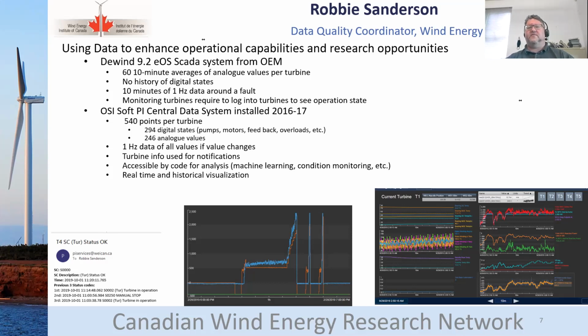Around a fault of the turbine, we would get higher resolution data, 1 hertz and sub-hertz data, for 10 minutes or less around the fault time, but no relevant historical data to go off of. So if you're trying to figure out whether your turbine was behaving the way it was before, it's very difficult to tell if that's indicative of normal operation or just how it was leading up to the fault.